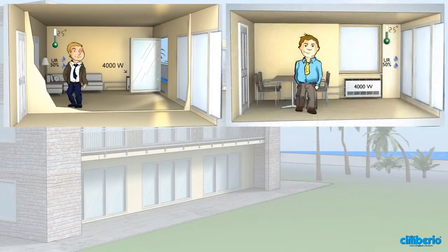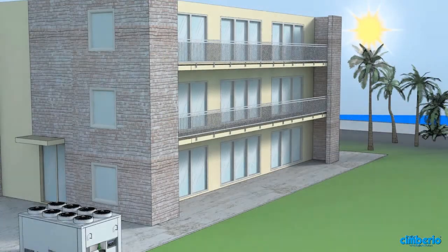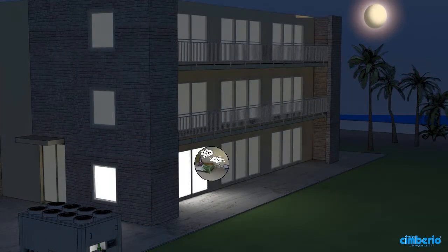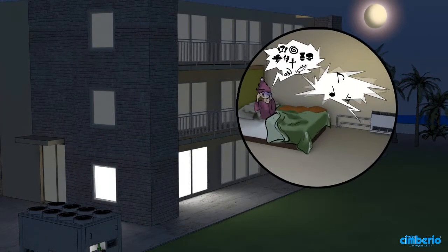Now both apartments have an acceptable temperature, but with a lot of waste. And that's not all. The plumbers increased the pump's flow rate, so those who live in the apartments near the boiler room will immediately notice the change. Too much noise, especially at night.